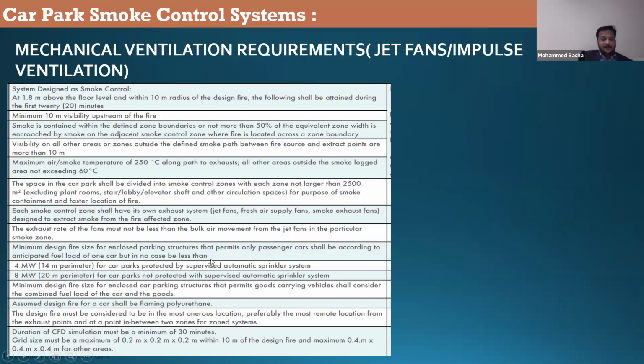I will tell you the reason. Of course, it is all related to Alpert's correlation equation, the ASHRAE calculator, whatever we were using now. See, when a car is typically burning, I showed you the peak HRR from NFPA 502. It can be anywhere from 4 megawatts, 8 megawatts, 10 megawatts. We don't know, it depends on the car: sedan cars, SUV cars you have nowadays, EV fire cars are there. Now, why are they saying 4 megawatts in the case of a supervised sprinkler system and 8 megawatts in the case of a non-supervised sprinkler system?